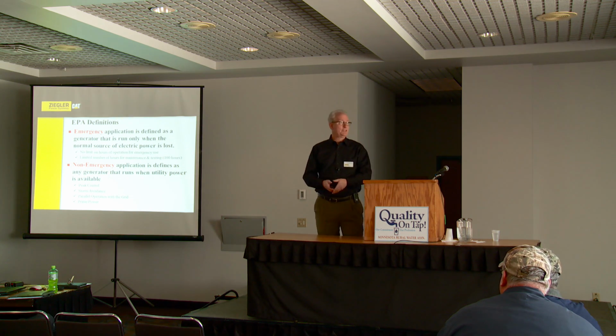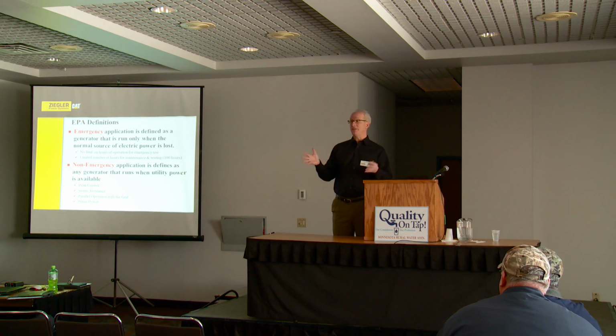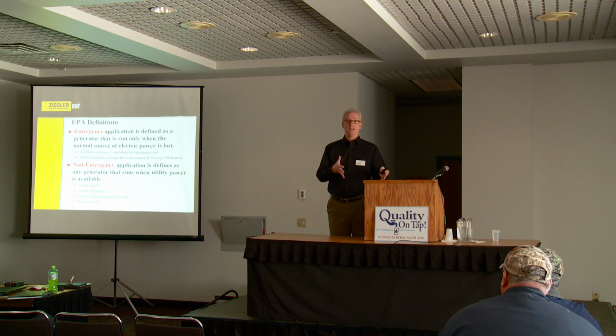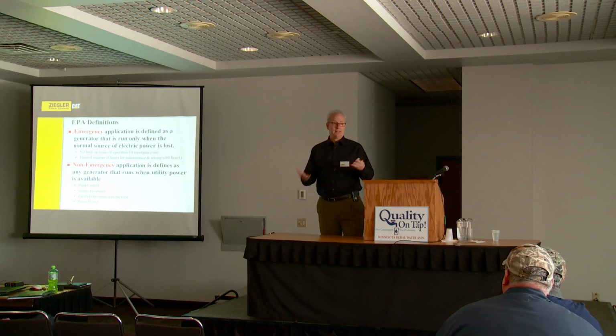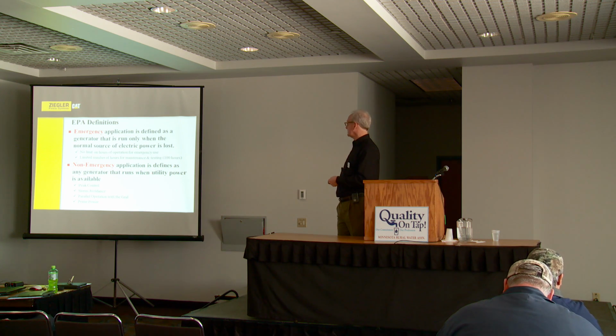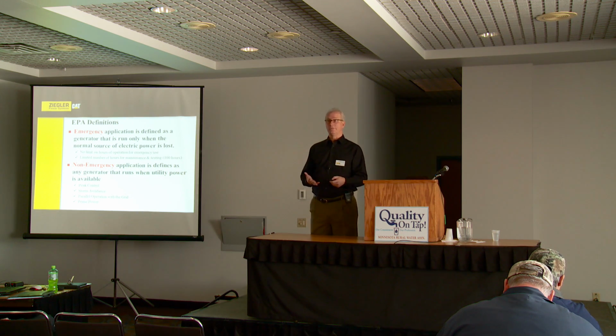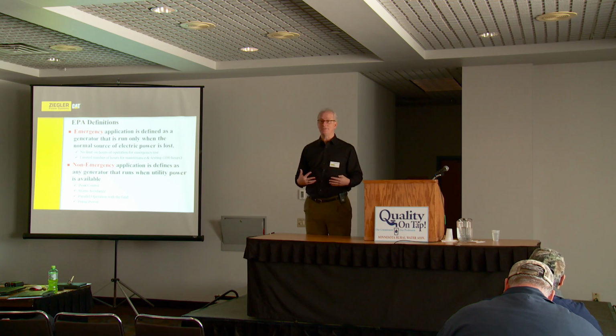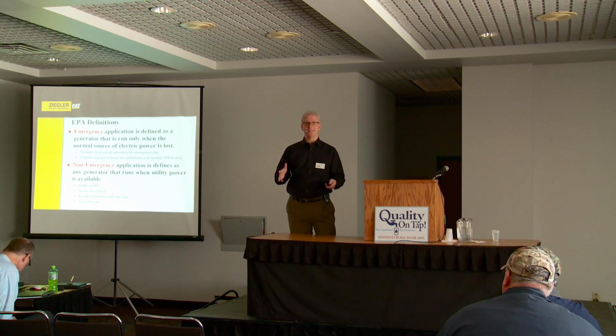And then the other side of the definition is that everything else is called non-emergency. In a lot of cases, if you're on a peak shaving program with your utility, a discount program where your utility might call you to run on certain days when there's more power need, sometimes the hot summer days, sometimes the cold winter days when there's a lot of electric heat, you can be non-emergency. The definition says that if you're on a program to get paid by your utility, if you're getting an incentive to run your generator, that's non-emergency. Even if you don't run your generator and you got that incentive, it's there. Even if you run that generator for 1 hour during the year, because of that, it's non-emergency.